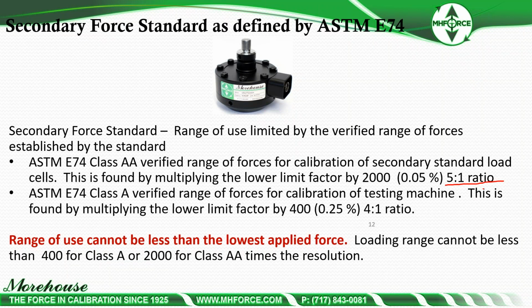When we look at what's actually going on, and then we look at the ASTM E74 Class A verified range of forces for calibrating a testing machine. This is found by multiplying the lower limit factor by 400, which gives us a 4-to-1 ratio. What's going on here is you go in, make your measurements. You take a lot of measurements, and then you calculate the standard deviation of all the deviations.